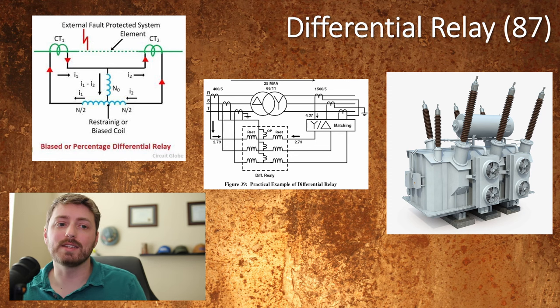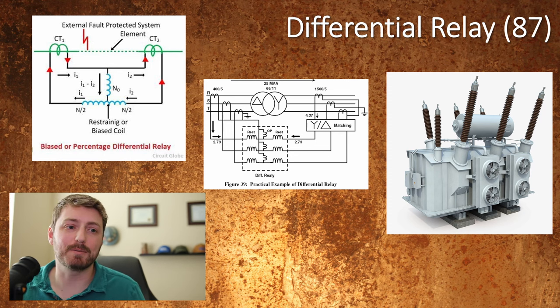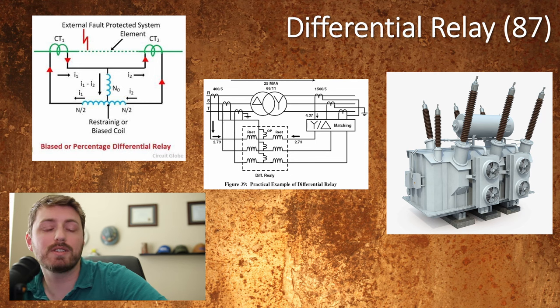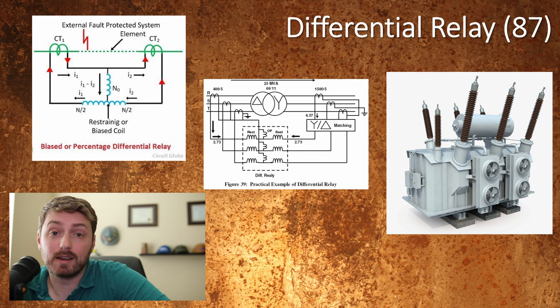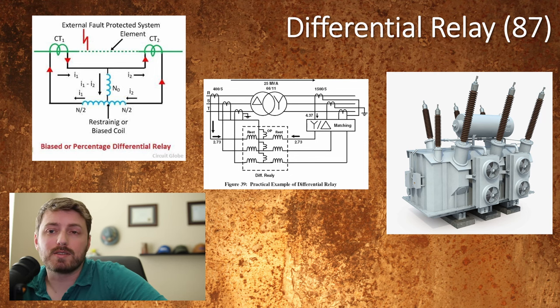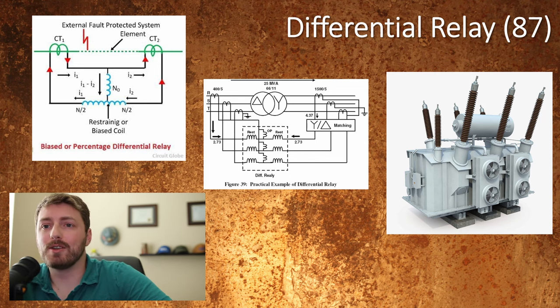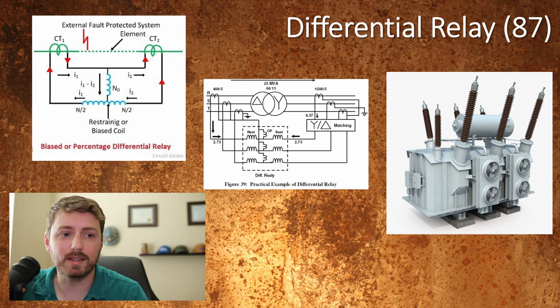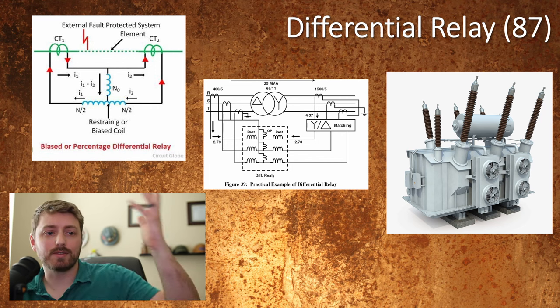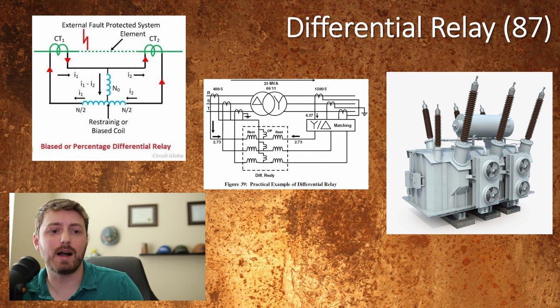Testing a 387 or a T90 can be a huge pain in the ass for some of the wild applications they shoehorn differential relays into. All these functions and many more have been performed for decades with microprocessor relays, solid-state relays, and electromechanical ones. Microprocessor relays just tend to do it better and are more reliable at this day and age, owing mainly to the fact that they can do tons of these functions all in one box with integrated SCADA, touchscreens, instead of having one old rusty box per function per phase.